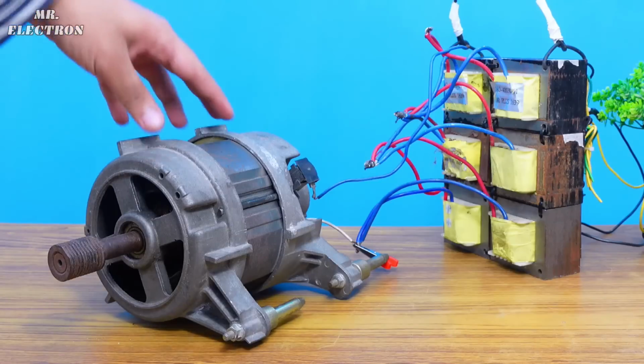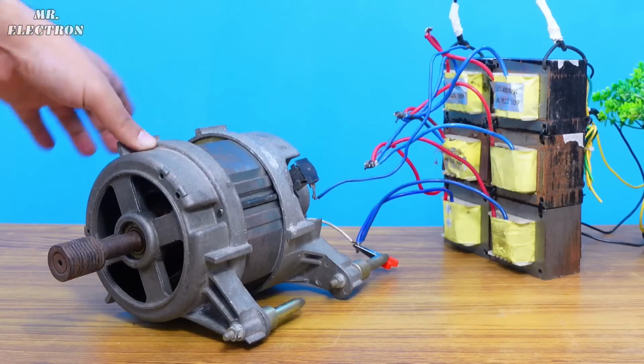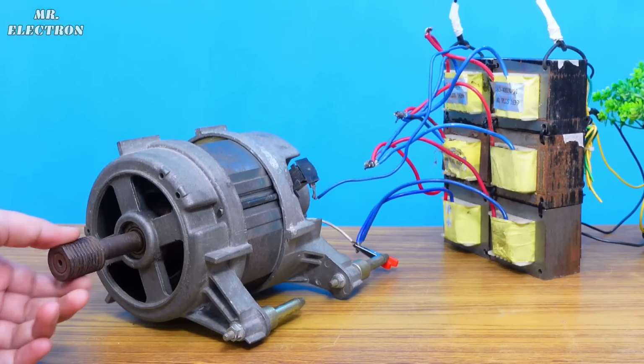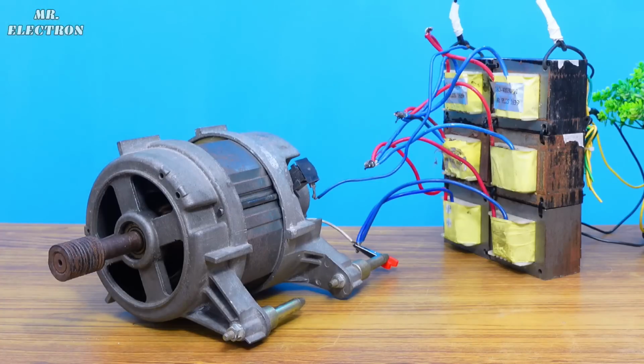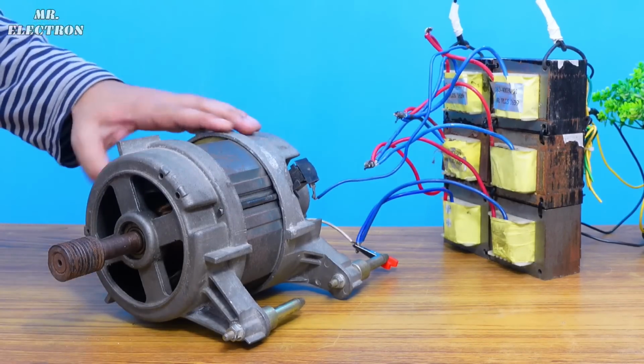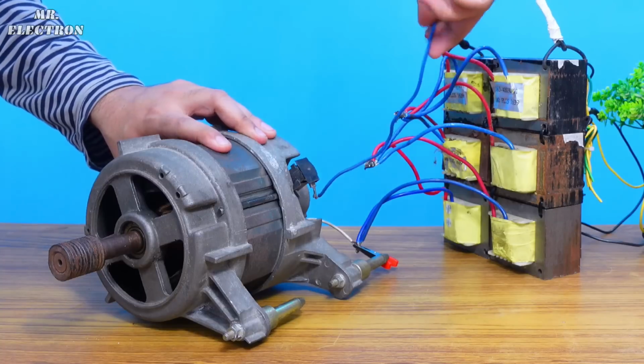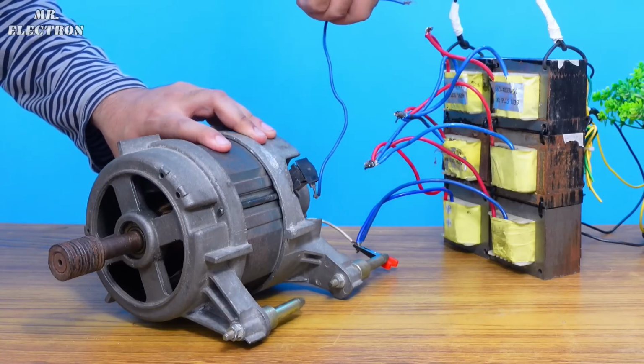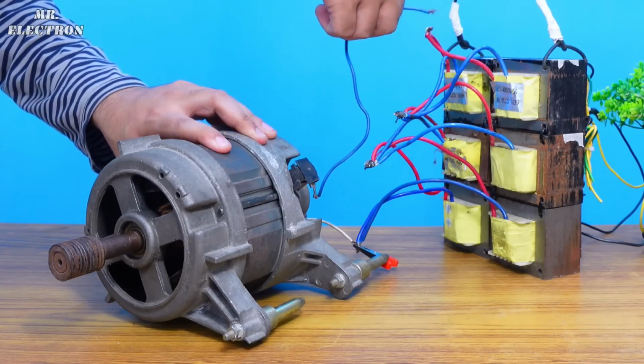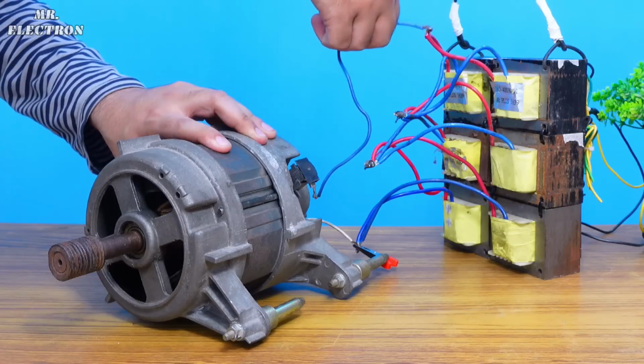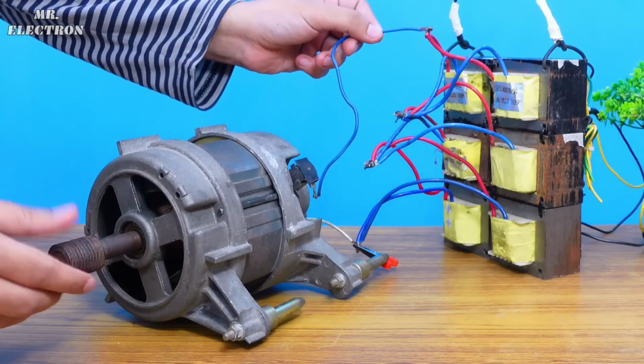Now here I have this 1 kilowatt 220 volts high-speed washing machine motor that I'm going to test with my huge transformer setup. Turning it on, holding it from the top because there is going to be a jerk, and finally touching this wire. I cannot believe it is unable to start even at 27 volts AC.